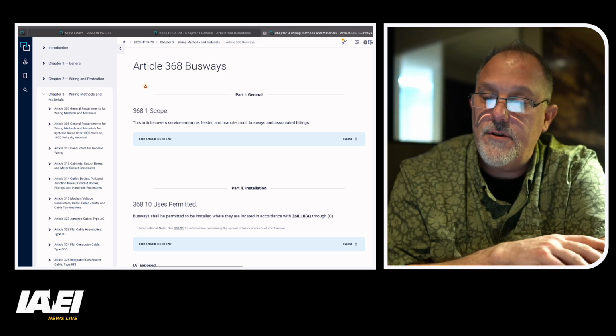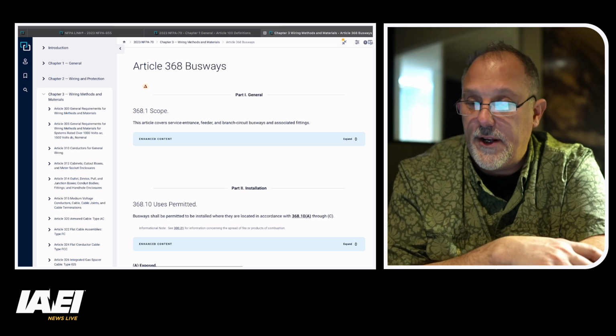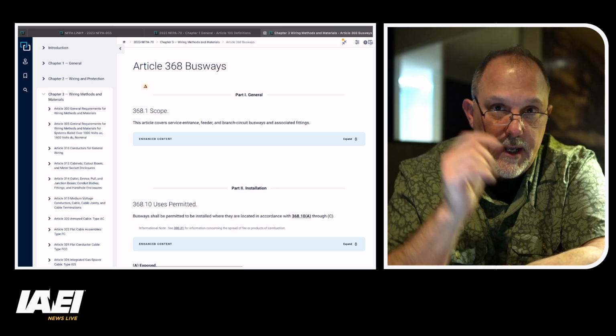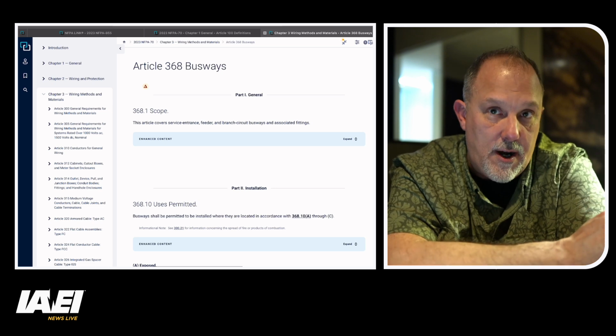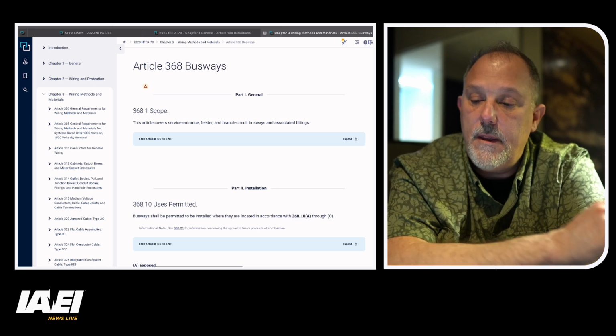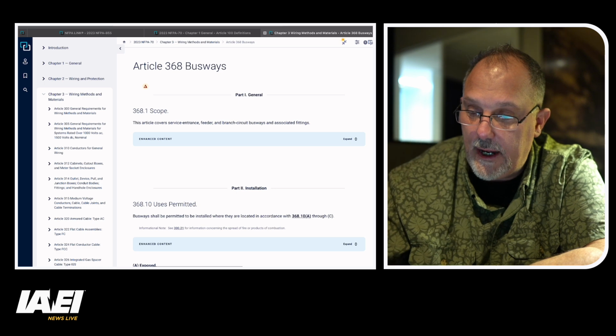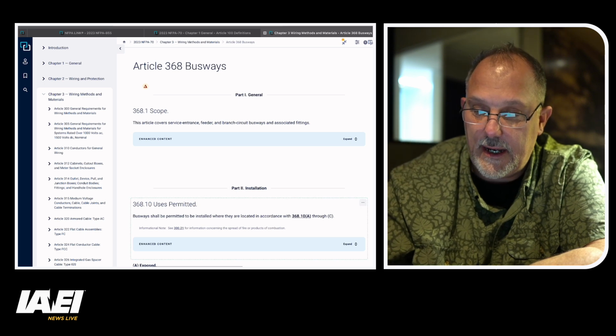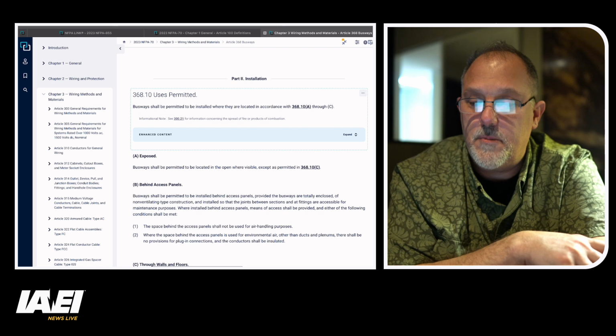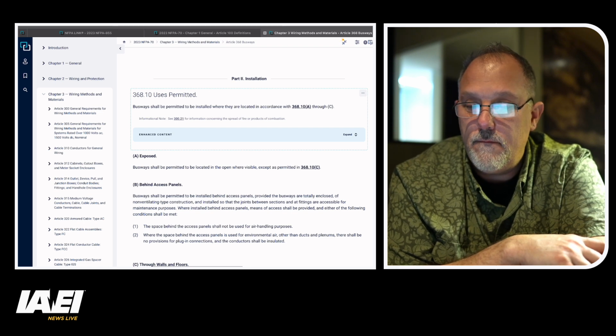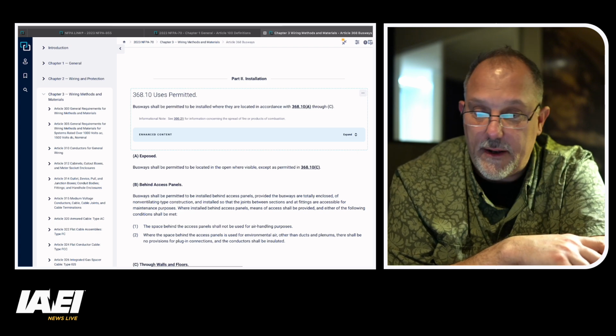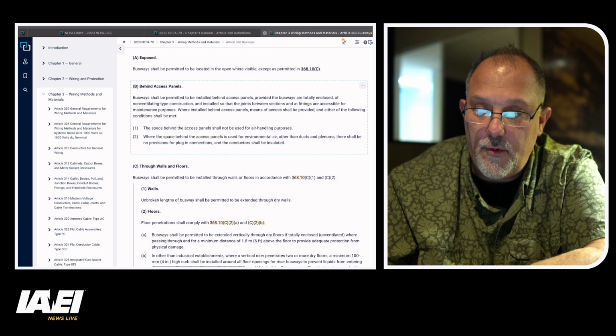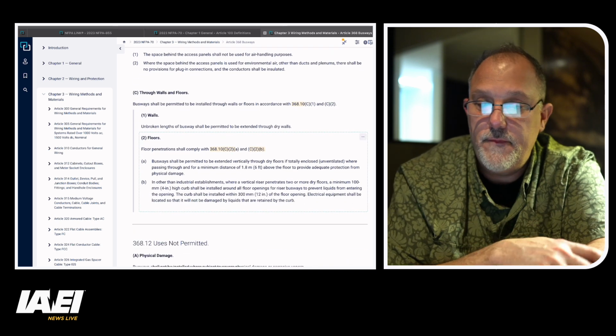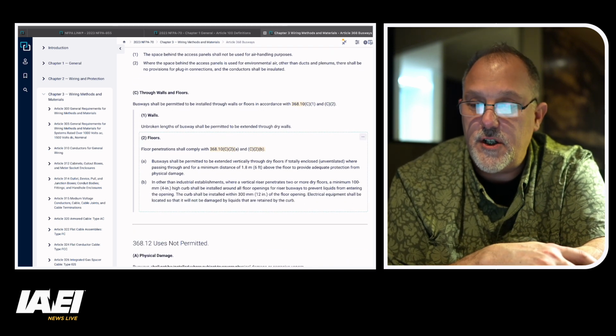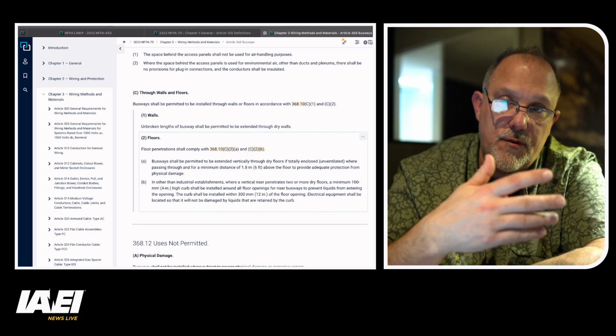We already said that it covers service entrance feeders and branch circuit busways and associated fittings. It doesn't matter if it's in a data center or not. It tells you that you can install it anywhere in accordance with 368.10(A), and A is exposed, open where visible, except as permitted in C, behind access panels, and you can go through walls and floors. So unbroken lengths of busway shall be permitted to be extended through dry walls.